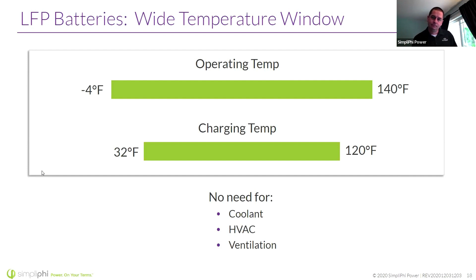where I'm trying to get my house cool with my batteries because the utility turned the power off. Now, charging temp's a little bit different story. There's a problem with lithium-ion in general, not a brand-specific problem, that the lithium ions don't like to be charged below freezing. And so you'll see, realistically, any lithium-ion battery maker will tell you do not charge it below freezing. Now, there are some exceptions, and we'll go over that when we get to our Amplify product, where we have a smart BMS. But as a rule of thumb, charging a lithium-ion battery below freezing is bad for the battery. It can cause permanent damage and lose capacity. So because of this wide operating temperature, we don't need coolant, heating or air conditioning, or ventilation.